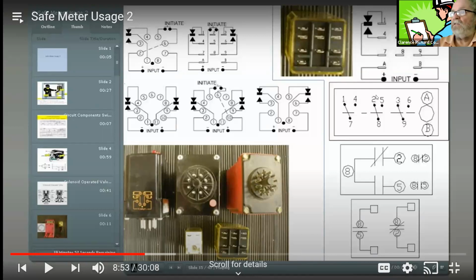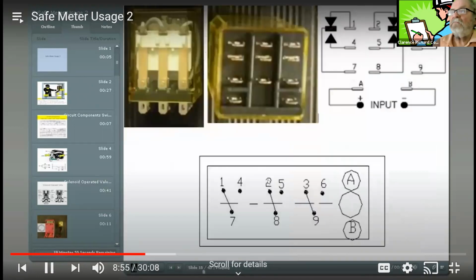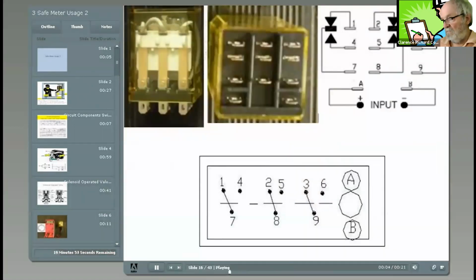So this is your relay. Normally open contacts, normally closed contacts. A 3PDT triple pole double throw relay. Whenever the coil is energized at terminals A and B, poles 7, 8, 9 stop touching 1, 2, 3 and now touch 4, 5, 6. The plus and minus polarity on the coil terminals refer to relays with DC voltage coils.